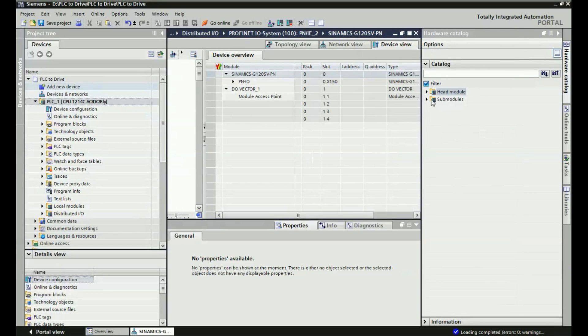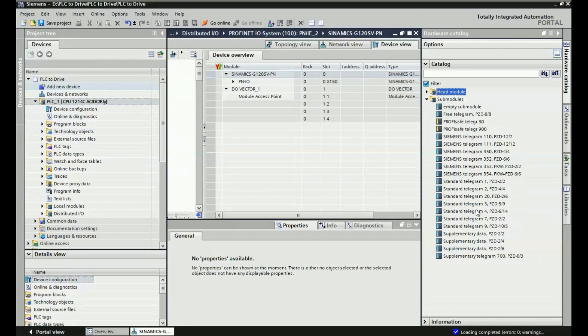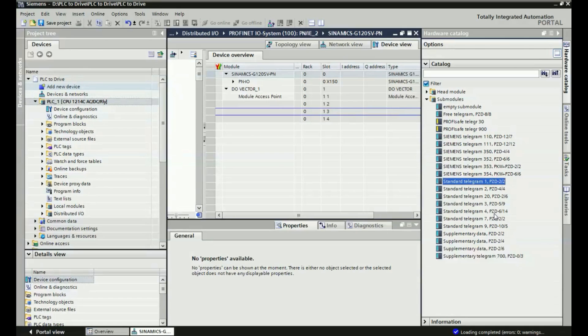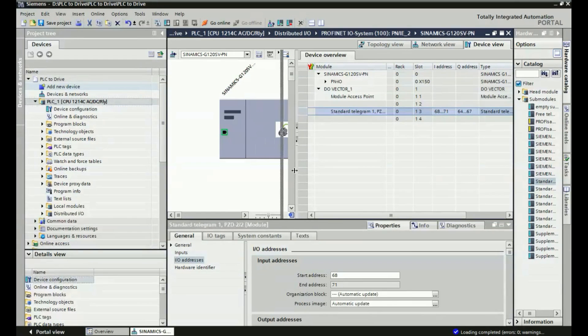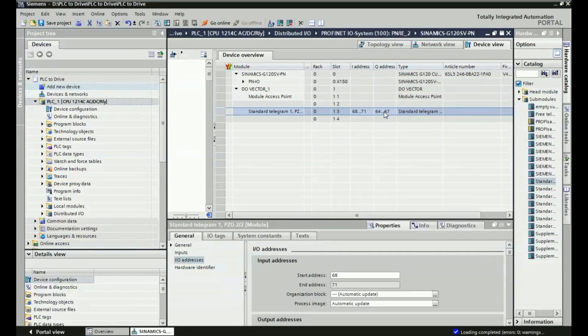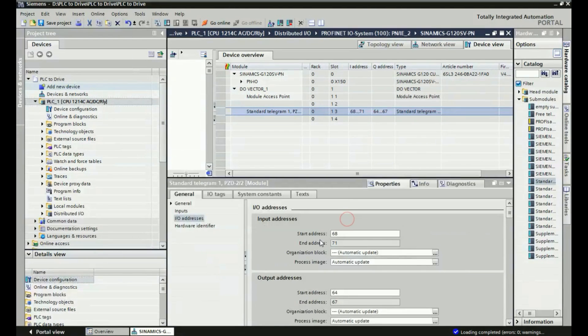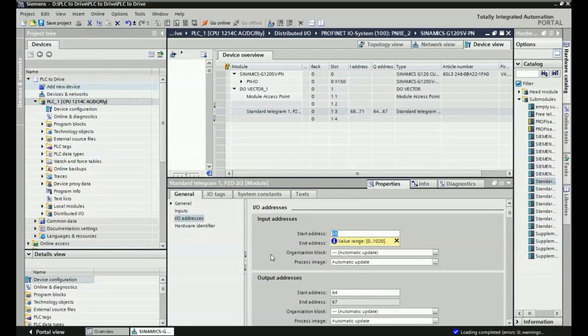Here we are getting different telegram options and from there we will use the standard telegram — 2x2, 4x4, and different telegrams are available. 2x2 means we are getting 2 input words and 2 output control words in this telegram. These input and output words can be used for controlling the drive from the PLC. I will double-click on this telegram and it will be added in the device overview. Here we are getting the input address and output address. We are using 2 input and 2 output; the input starting address is 68 and the output starting address is 64.